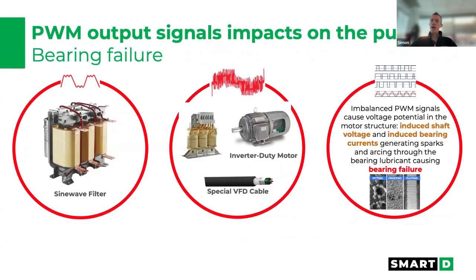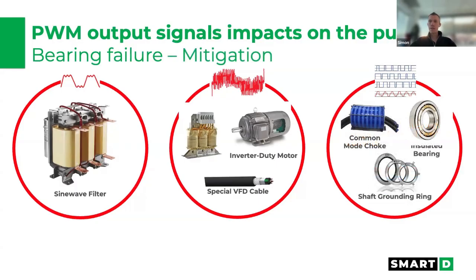Now, you can put a choke there, but you're not going to remove your common mode. The common mode is caused by the core of the PWM. And so all you can do is really try to get that common mode to go elsewhere. This is where the insulated bearing is trying to not impact the bearings. The shaft grounding ring is trying to get the common mode to go through that ring instead of through the bearings. And the common mode choke will do what it can to get some through that choke instead of through the bearings. But you're really not addressing the root cause in all of these cases.